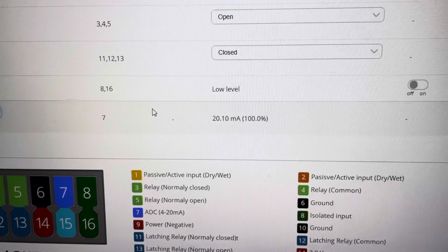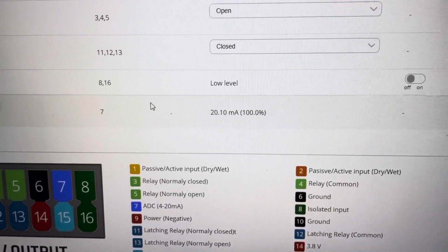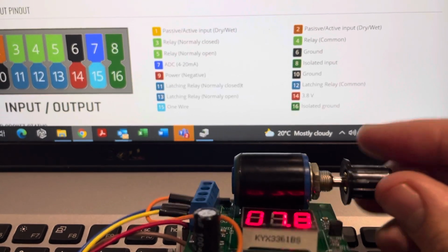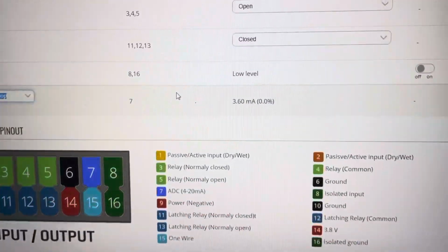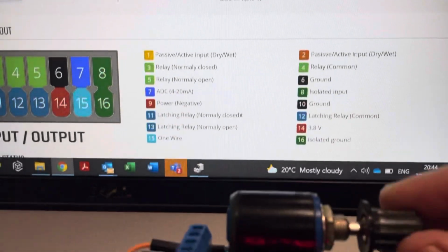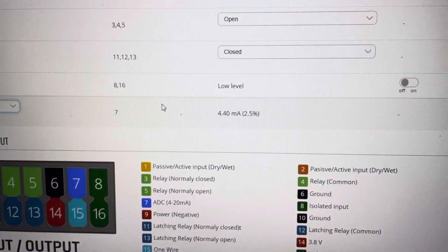And there, 20 milliamps you can see is the maximum, and the reason it's 4 on the low end, if I go right down again and turn the dial down, is if the signal is dead or too low, then it wants to know that it's bad. So basically that's why 4 is the lower limit. And considered below naught. So there, anything below 4 is naught. As I creep up to 4 again, it'll be just about 1%.